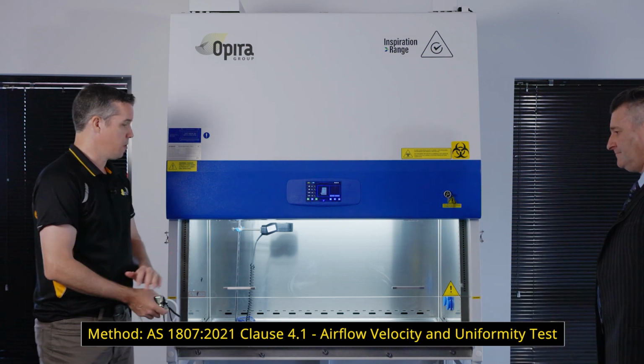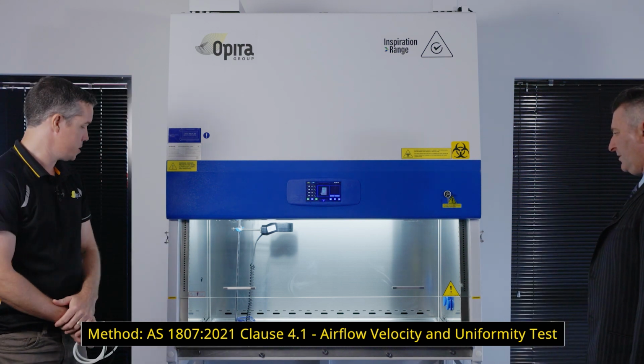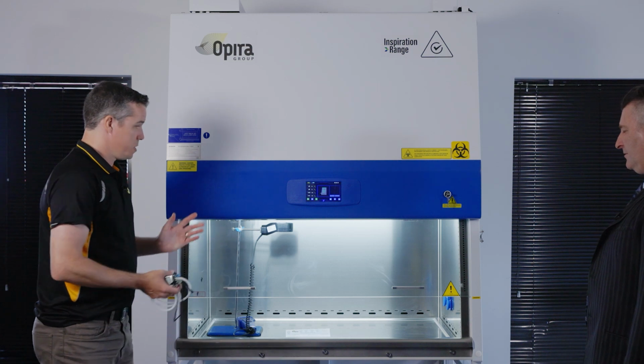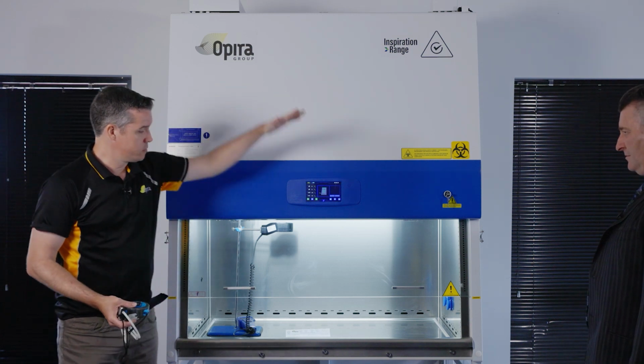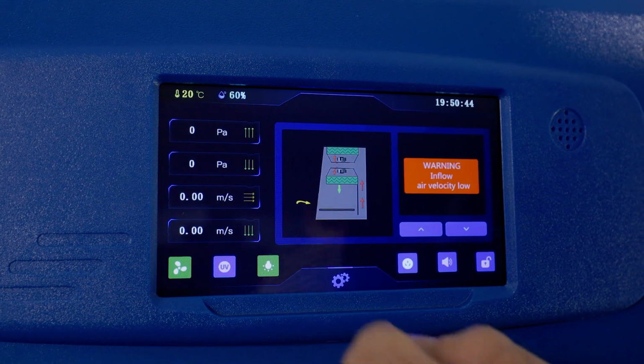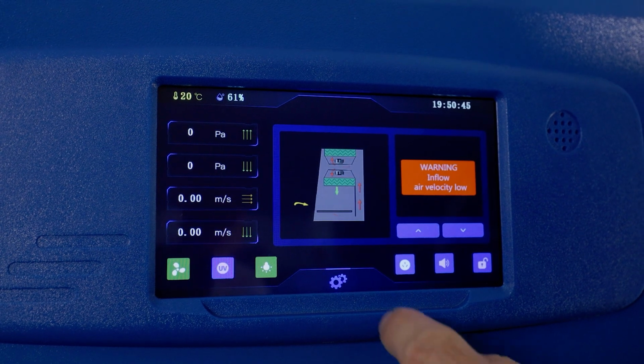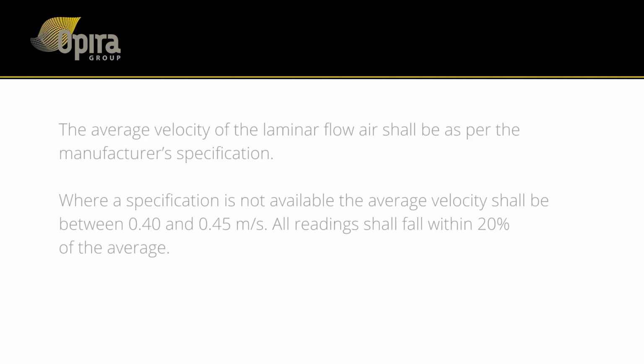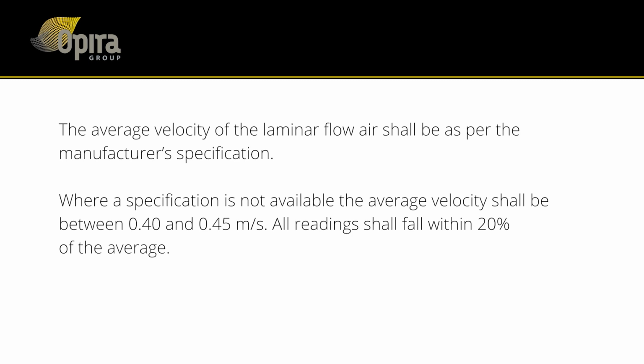Yeah, in clause 4.1 of the 1807 standard that you mentioned, Scott, we're measuring the airflow from the laminar flow filter down over the workspace. There's a requirement for the airflow to average between 0.4 and 0.45 meters per second, as well as having a 20% margin of error either side.